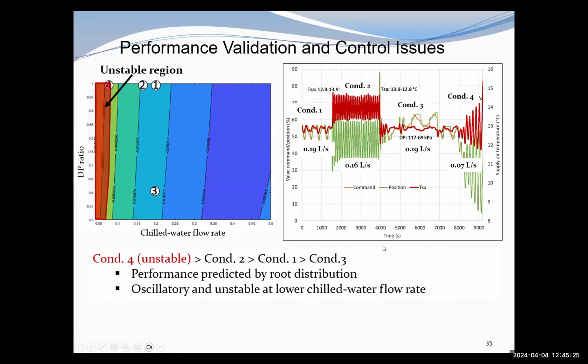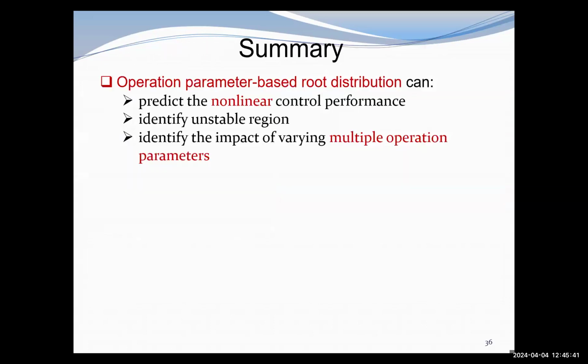So we can see that the performance can be predicted by the root distribution, and for the cooling coil valve control system, oscillatory and unstable behavior may happen at lower chilled water flow rate conditions. So here we have the summary. The operation parameter-based root distribution can predict the nonlinear control performance and help us identify unstable ranges, and also identify the impact of multiple operation parameters, such as how the fan speed and duct static pressure change will impact the fan speed control, and how the chilled water flow rate change will impact the cooling coil valve control.